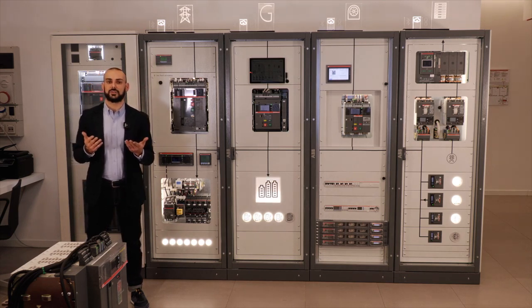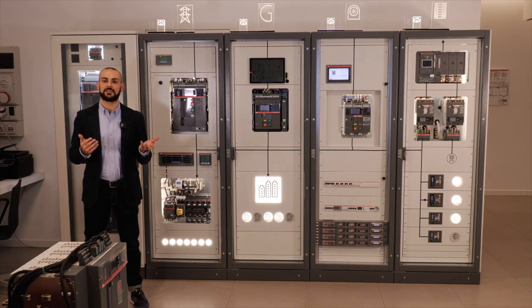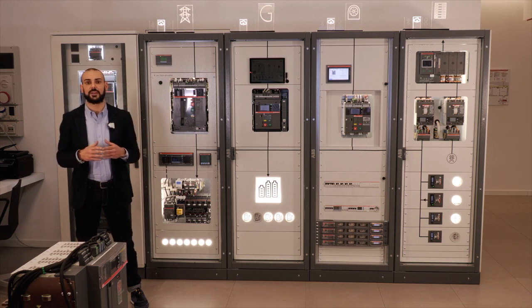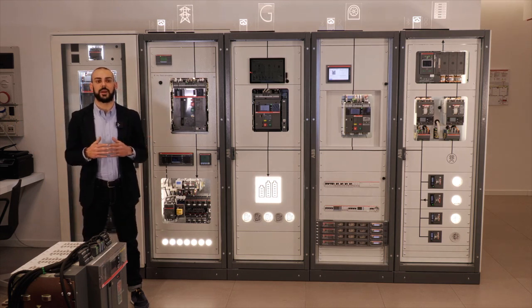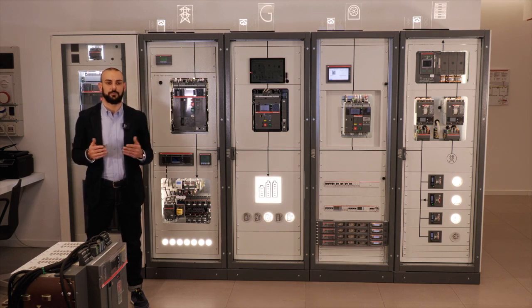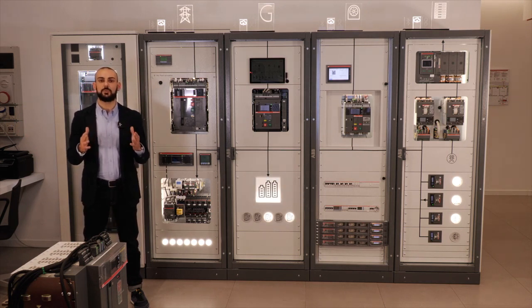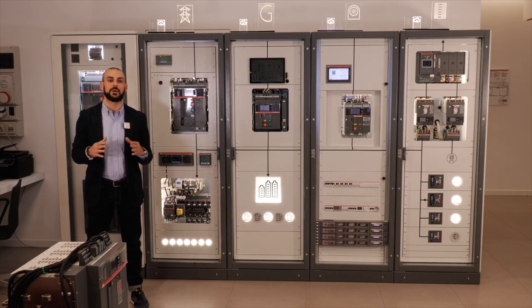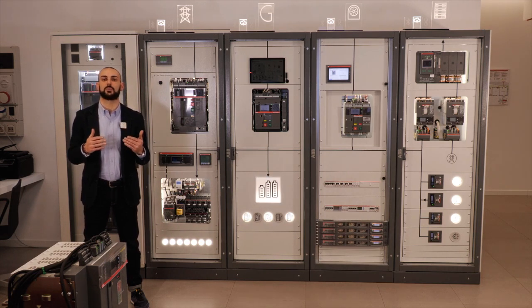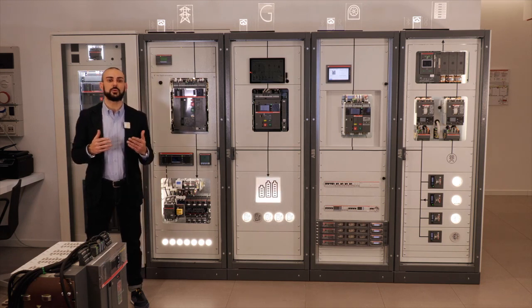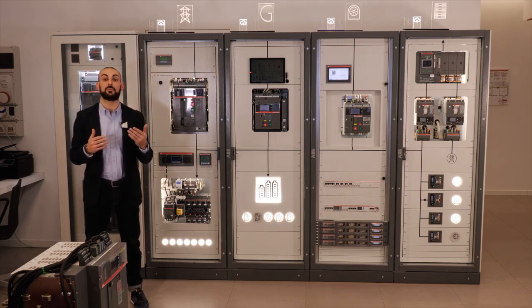Let's start with the protection devices ranging from 160 amps of nominal current all the way to 6,300 amps: ABB molded case circuit breaker called Tmax XT and air circuit breaker called Emax 2. Both offer the same user experience over the whole range. These devices can perform class 1 accuracy measurements certified according to IEC 61557-12, including a network analyzer able to monitor up to the fifth harmonic of voltage and current.